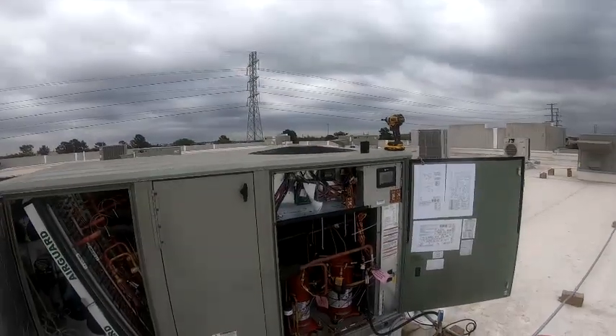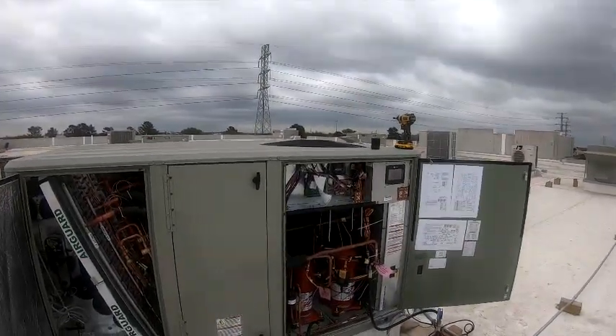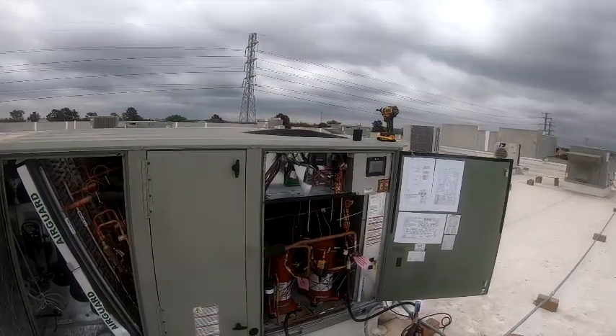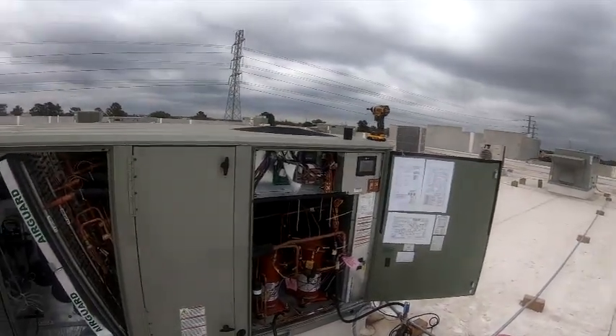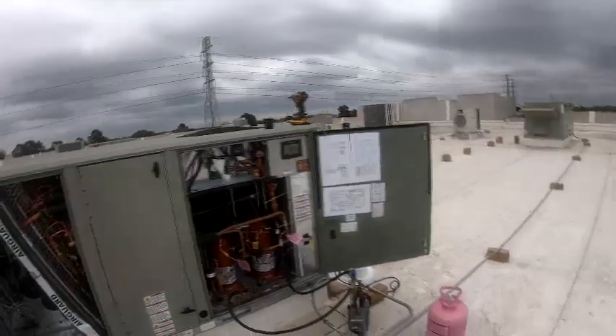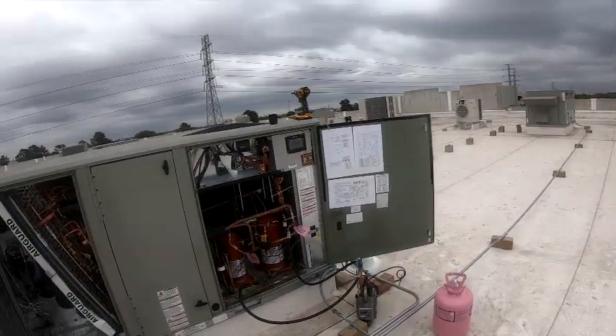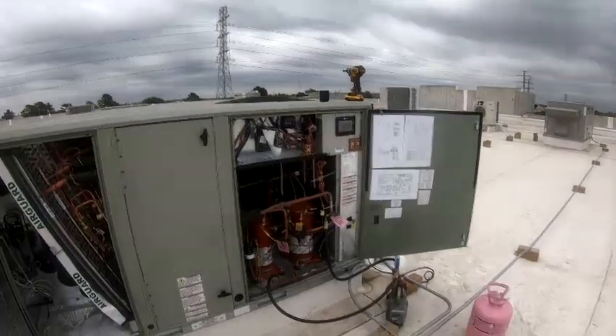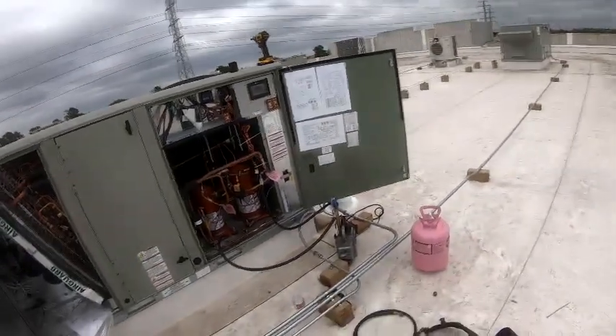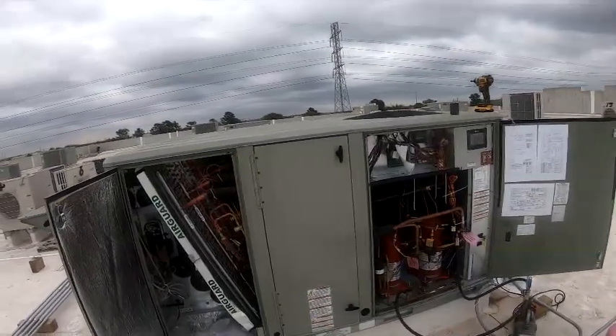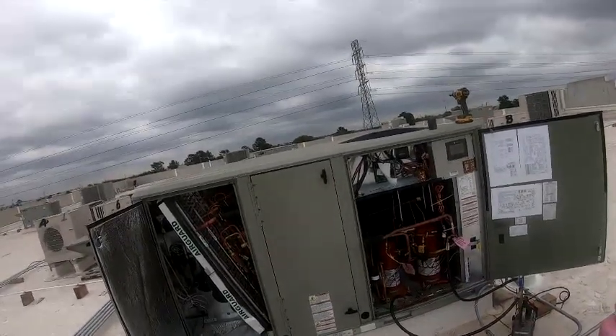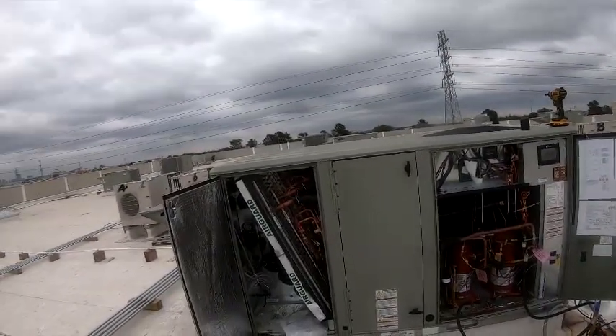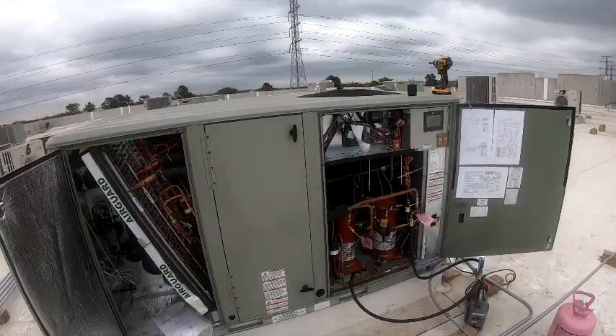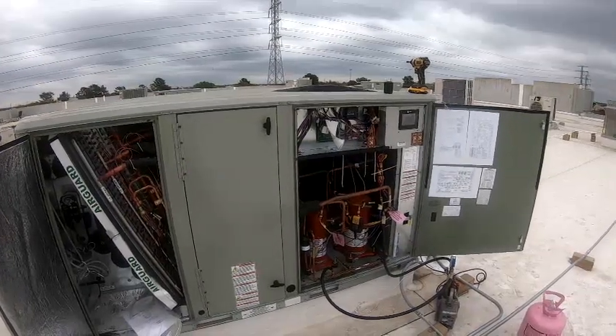Down about 730 microns. It's only been probably between 5 and 10 minutes, so we can get that down to 500. Got a couple more I need to check on. I think I've got a bad phase monitor on one of these units. All right, so we're chilling at 730. Let's see if we can get it down.